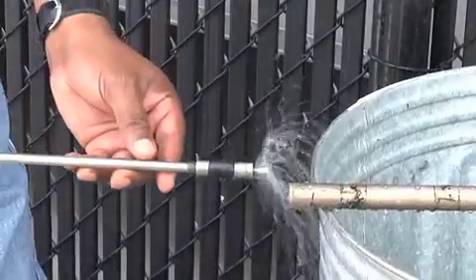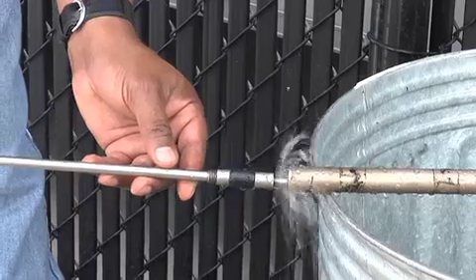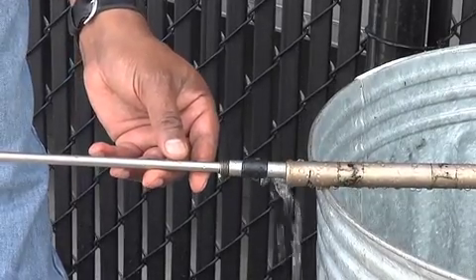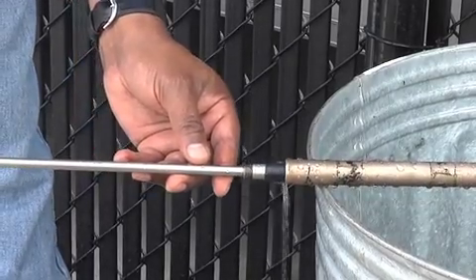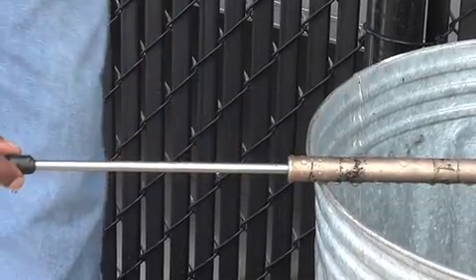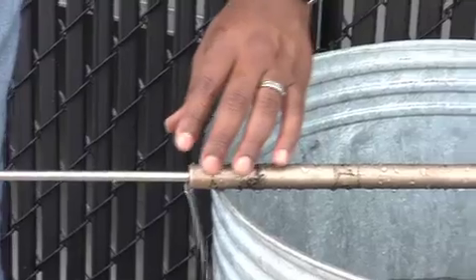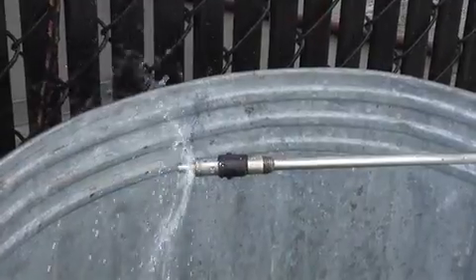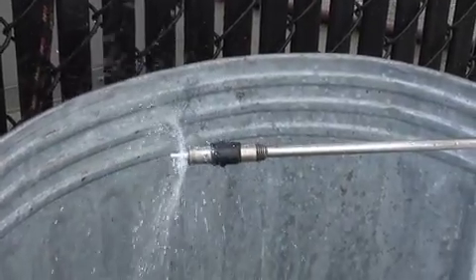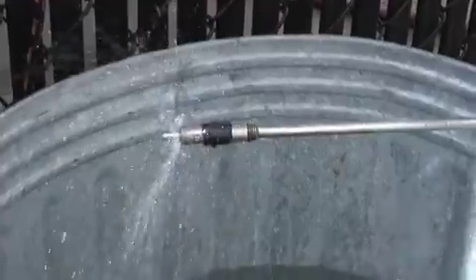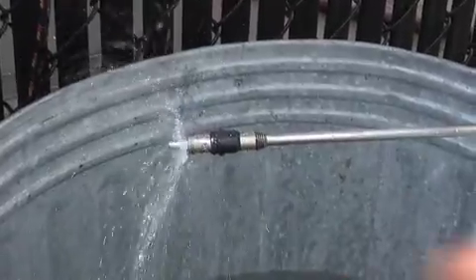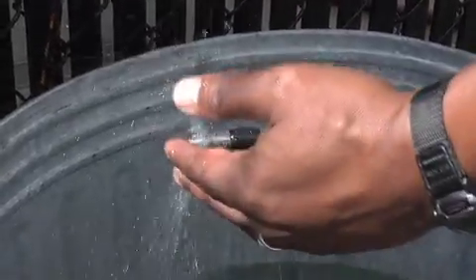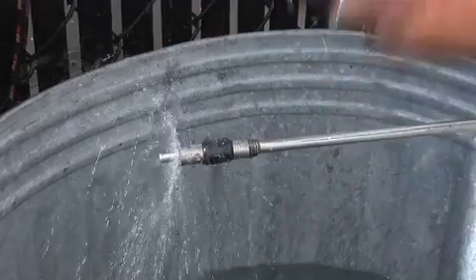To show you how IRIS actually works, this is the IRIS probe. Being that this is an ultrasonic, we do need a medium for the sound to travel through. By using the water and having the water spin, I'm able to get 360-degree coupling.